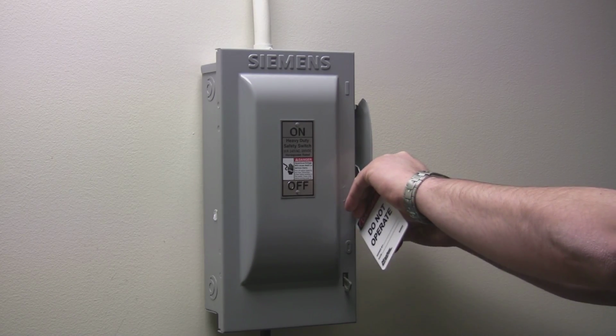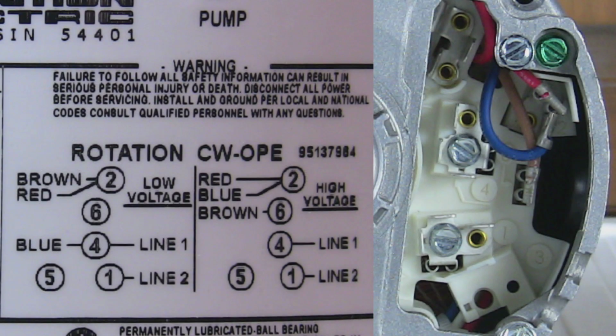Number 2. Identify the 3 wires coming from the machine. These wires are coming out of the conduit that's attached to the motor and are typically black, white, and green. Move these wires aside in order to have a clear view of the terminals within the motor. Number 3. Look at the wiring diagram and notice that the brown wire and red wire within the motor must be attached to terminal 2. Confirm this on the terminals. Number 4. Refer back to the wiring diagram and see the motor's blue wire is to be connected to terminal 4. Confirm this on the terminals.